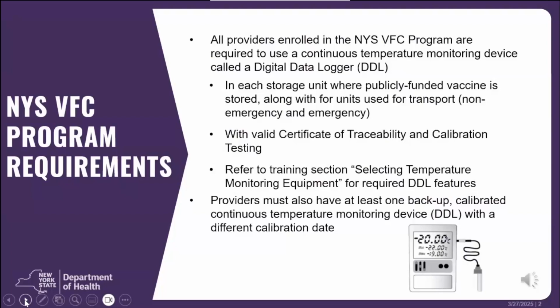Providers are also required to have at least one backup calibrated continuous temperature monitoring device or DDL with a current certificate of calibration for each storage unit holding publicly funded vaccine. The backup devices should be used in case of equipment failure or when your calibration testing is due for your primary devices. Your backup devices should have different calibration dates than your primary devices.